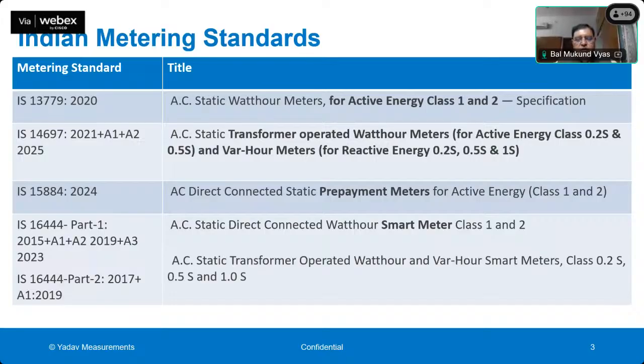So all these prepayment meters have a switch inside the meter to connect and disconnect. That is called a connect and disconnect switch, or a load control switch. And that type of meter has to be tested as per IS 15884. And there is a recent edition of this standard which was published in 2024. Another two very important standards are for smart electricity meters, smart meters.